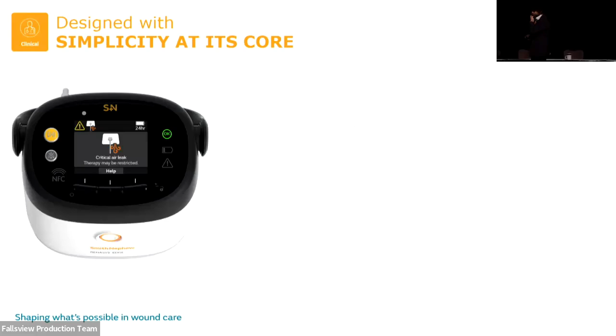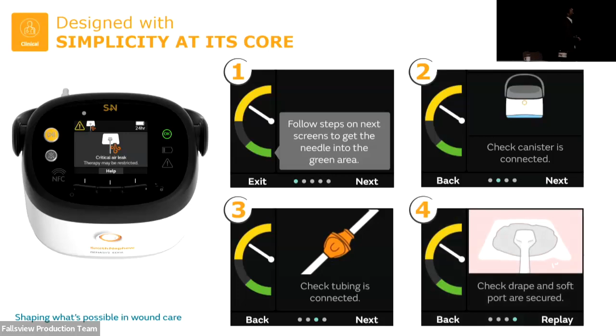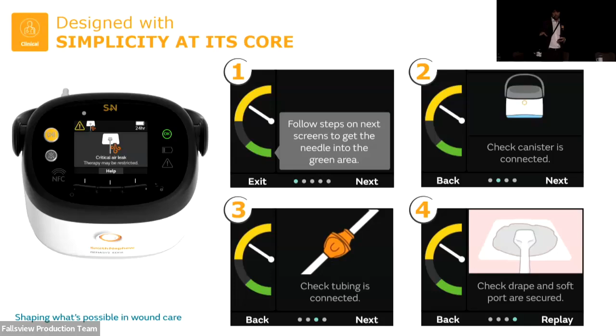Let me give you an example. When you have a leakage alarm, the pump automatically brings the alarm screen on, and it asks you to click this button to get help. And then you see step one, follow the different steps. So this is a live flow meter, right? Our objective is to bring that one down to the green part. And say, okay, what do we do? Think about not experienced nurses that you need to train. First thing, you see, check the canisters. The second one would be check if the connector is actually connected correctly. And lastly, you see the animation on the pump to check the drape. And by the time you're checking the drape, trying to identify where the leak is, the flow meter will just go back to the green position, and will give you a clear signal that the leak is resolved and therapy is going on.